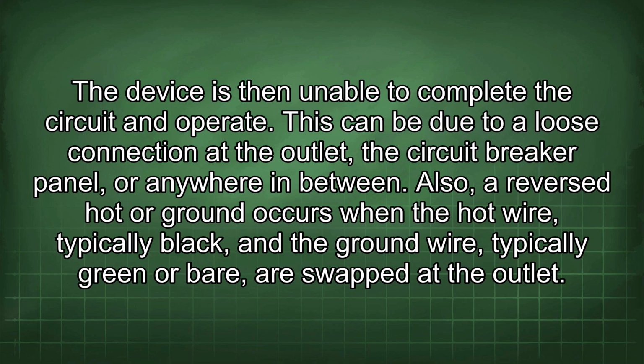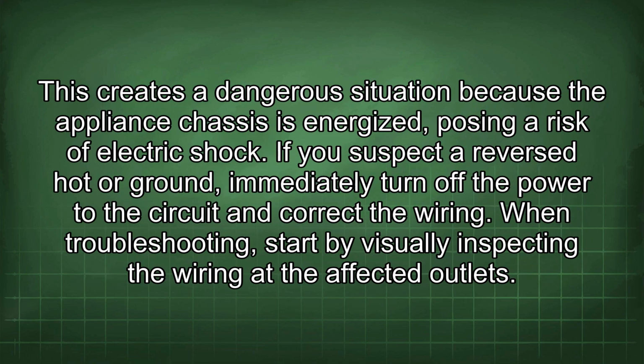Also, a reversed hot or ground occurs when the hot wire, typically black, and the ground wire, typically green or bare, are swapped at the outlet. This creates a dangerous situation because the appliance chassis is energized, posing a risk of electric shock. If you suspect a reversed hot or ground, immediately turn off the power to the circuit and correct the wiring.